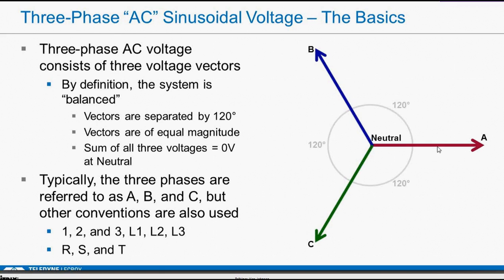Three-phase voltage is really the same as single phase. I've only had one vector before, and now I have three. They're separated by 120 degrees by definition, and they're all of equal magnitude. Therefore, if I sum all these components up, I get zero at the neutral. That's by definition. The three phases are typically referred to on the line side as A, B, and C, but lots of other conventions are used.